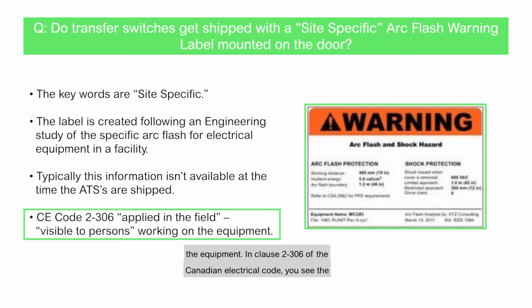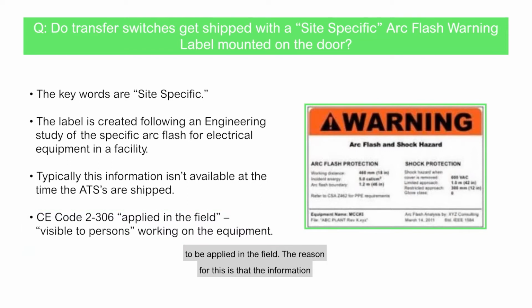In Clause 2-306 of the Canadian Electrical Code, the key phrase is 'applied in the field.' There is a label required, but it needs to be applied in the field. The reason is that the information generally comes from an engineering study, and that study is site-specific. It's dependent on the overcurrent protection devices ahead of the transfer switch and the settings of those devices.